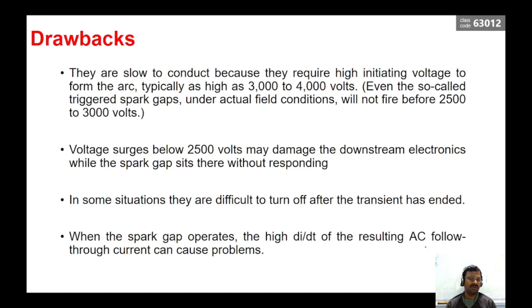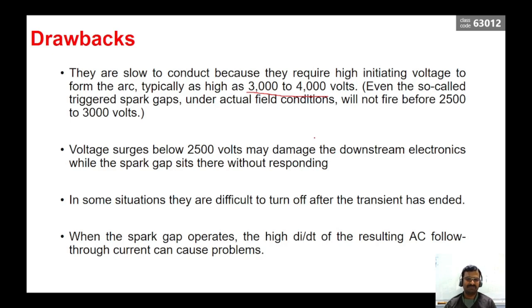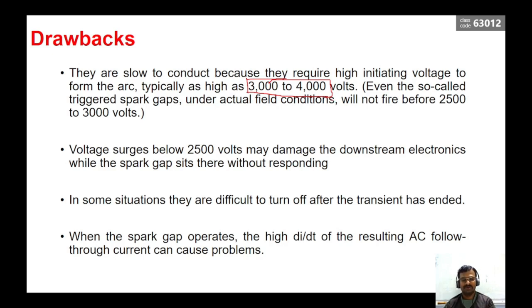From this discussion, you can understand how the spark gap mechanism works. To create a spark between two electrodes, we need a very high voltage. But the devices which we are going to protect may get affected before this voltage is reached. For example, the spark gap device is waiting for 3000 to 4000 volts, but the device which needs to be protected may get damaged at 1000 or 1500 volts itself. So this is one big drawback — spark initiation requires a very high voltage, but the device we are protecting has a very sensitive voltage level.